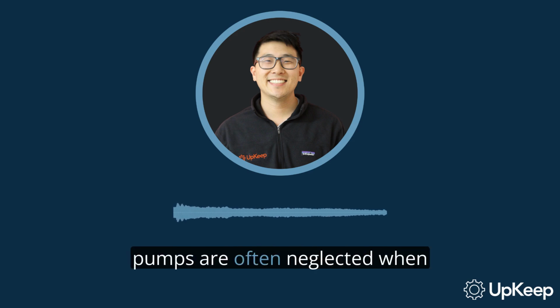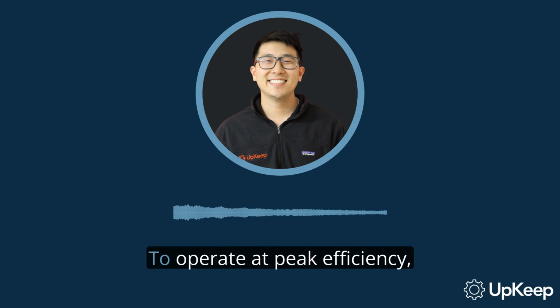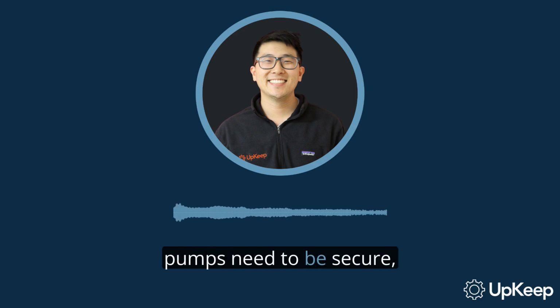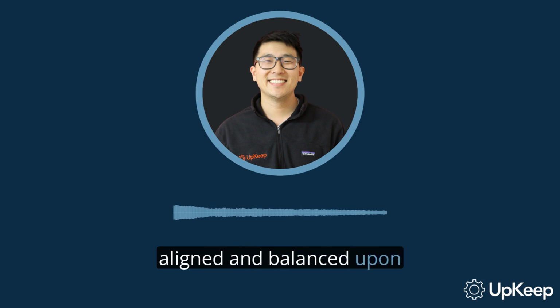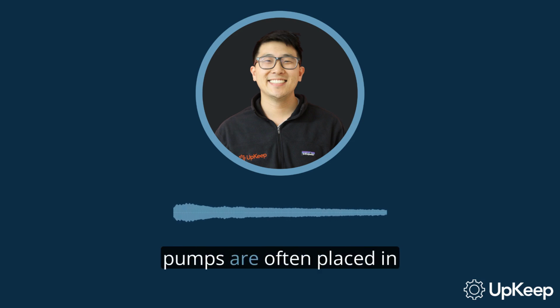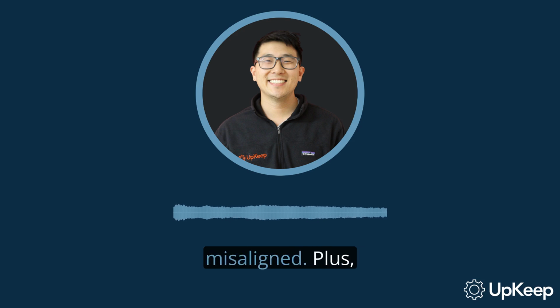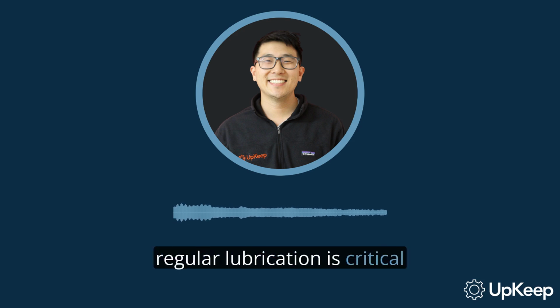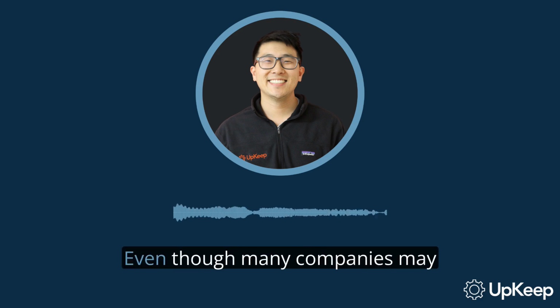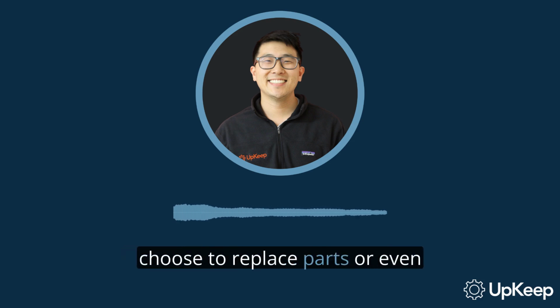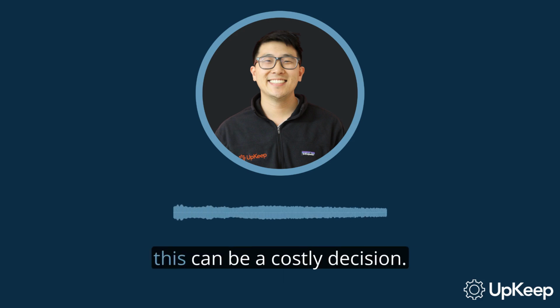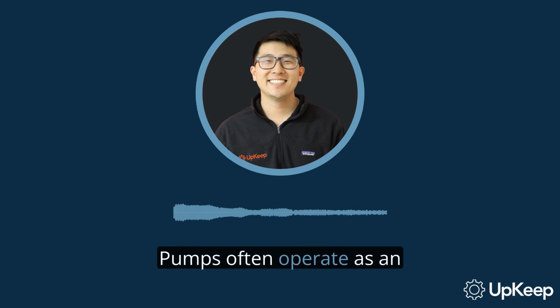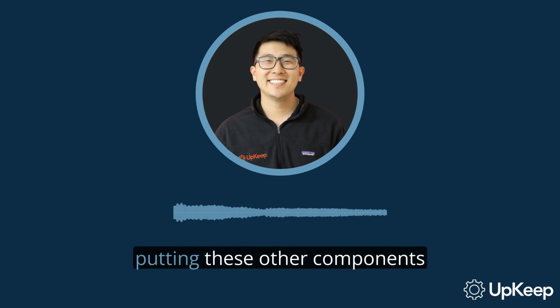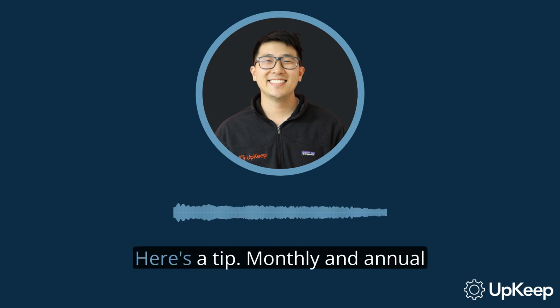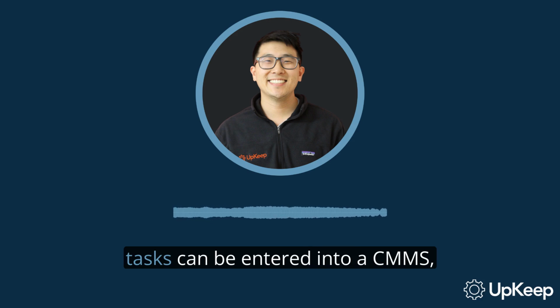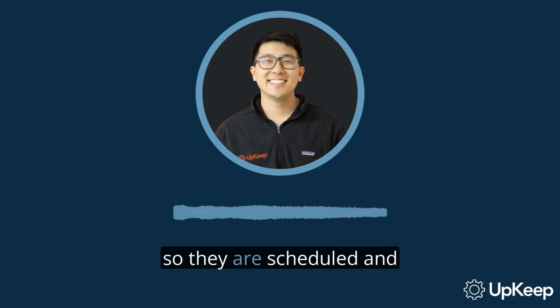Sadly, pumps are often neglected when it comes to preventive maintenance. To operate at peak efficiency, pumps need to be secure, aligned, and balanced upon installation. In reality, pumps are often placed in precarious locations or misaligned. Plus, regular lubrication is critical to efficient and smooth operation. Even though many companies may choose to replace parts or even pumps instead of maintaining them, this can be a costly decision. Pumps often operate as an integral part of a larger system, putting these other components at risk for failure. Here's a tip.